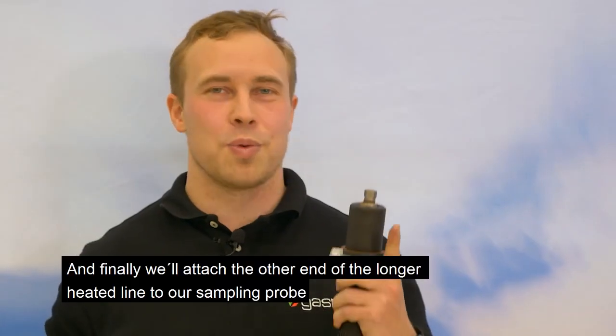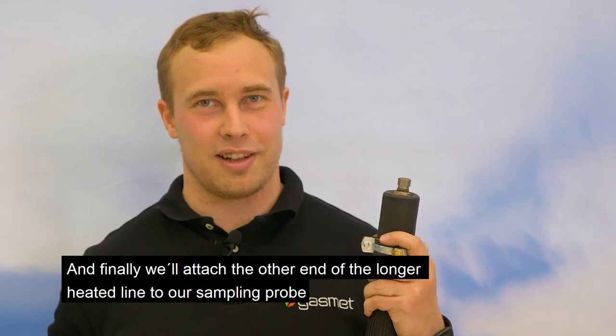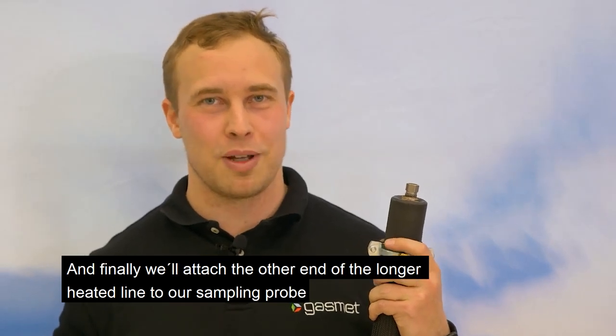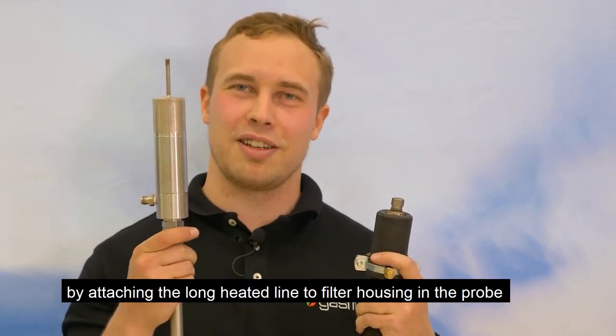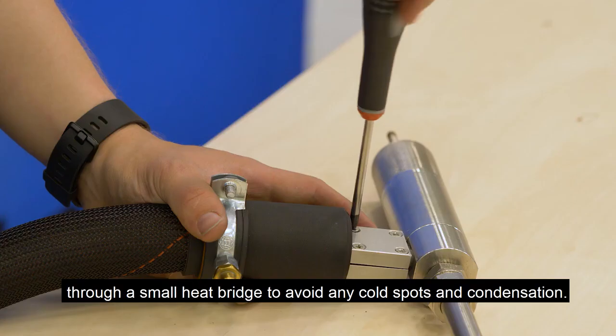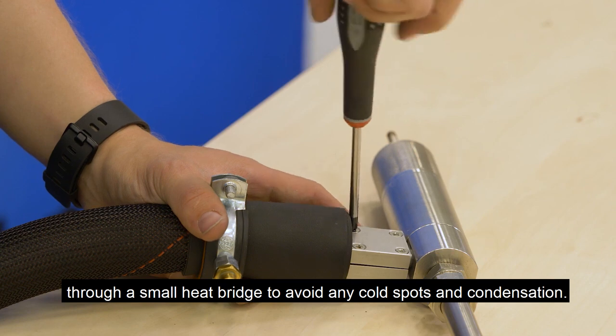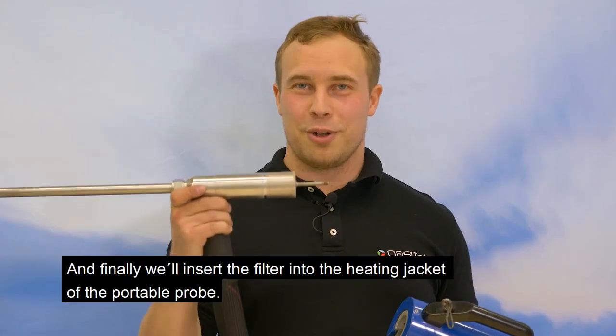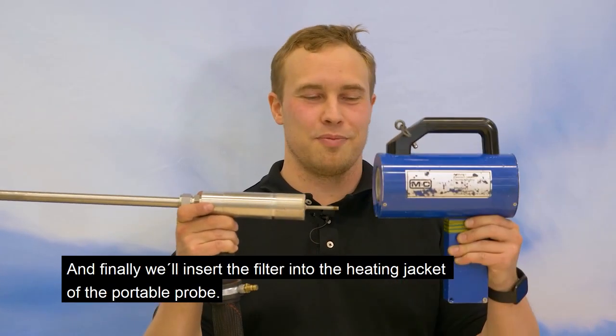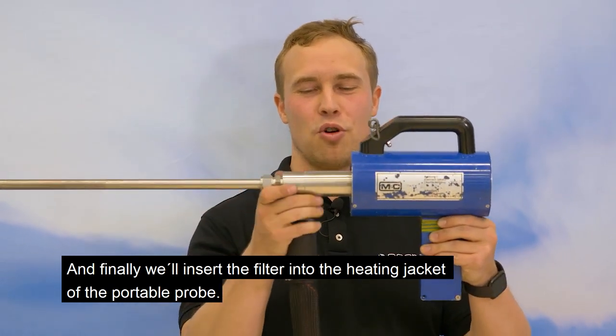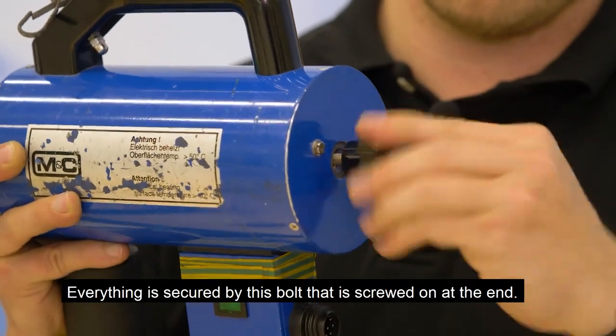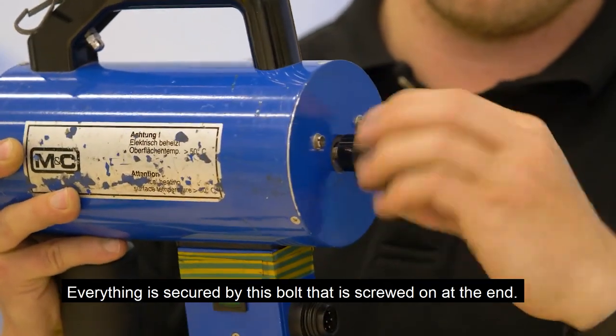And finally we'll attach the other end of the longer heated line to our sampling probe by attaching the long heated line to the filter housing in the probe through a small heat bridge to avoid any cold spots and condensation. And finally we'll insert the filter into the heating jacket of the portable probe. Everything is secured by this bolt that is screwed on at the end.